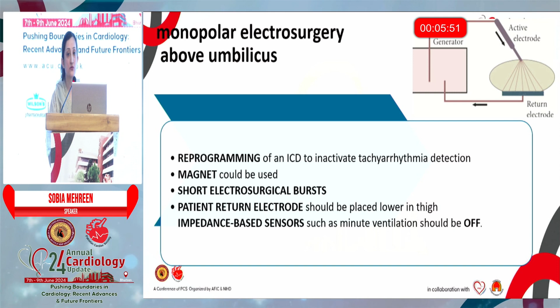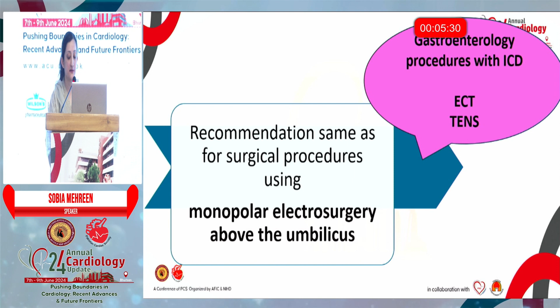A magnet can be applied, limiting the electrosurgical procedure to short electrosurgical bursts and placing the return electrode away from the device, and the rate response sensor should be turned off. In case of gastroenterology procedures, including endoscopies, colonoscopies, and procedures using ICDs, along with procedures using ECTs and TENS, the recommendation is the same as for procedures using monopolar electrosurgery above the umbilicus.